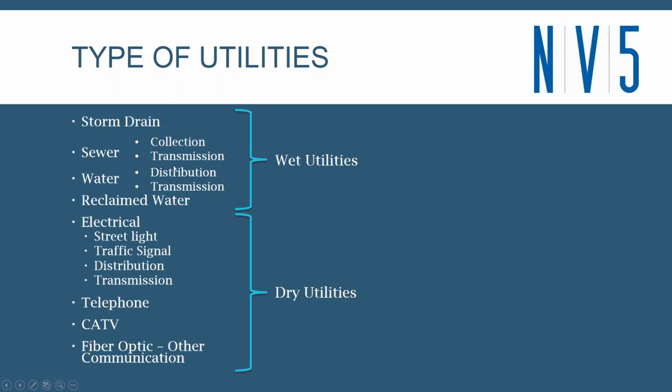Now, typically, unless the system's pressurized, these are gravity and really can't go uphill unless you've got some kind of pressurized water system. Reclaimed waters are usually pressurized. Force mains are usually pressurized. Okay. Now, a force main's a little bit different animal. It's a transmission. They treat it like a transmission main. But these are the different types. And I think I covered everything, but somebody will always come up with something new.